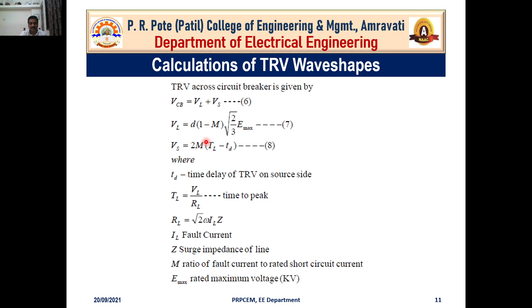Now VL is represented by the equation D into 1 minus M square root 2 by 3 E max, whereas VS equals twice M into TL minus TD, where TD represents the time delay of TRV on the source side. From TL we can find TL equal to VL by RL, that is the time to peak. RL equals square root 2 omega IL Z. IL is your fault current, and Z is the surge impedance of that transmission line. M is the ratio of fault current to rated short circuit current, whereas Emax is the rated maximum voltage in kV. This way we can find the TRV across the circuit breaker.